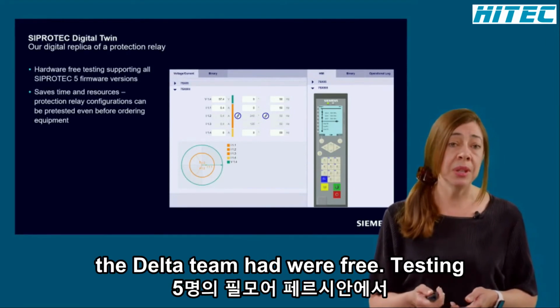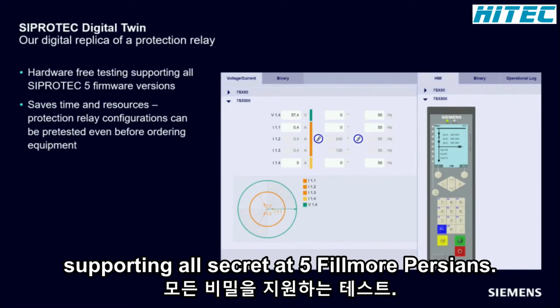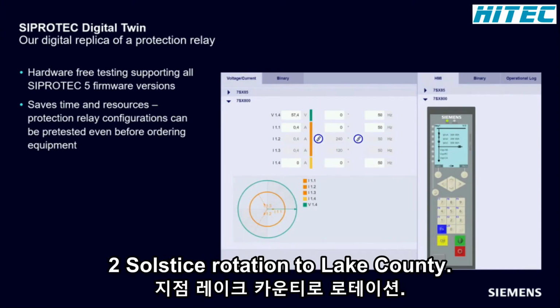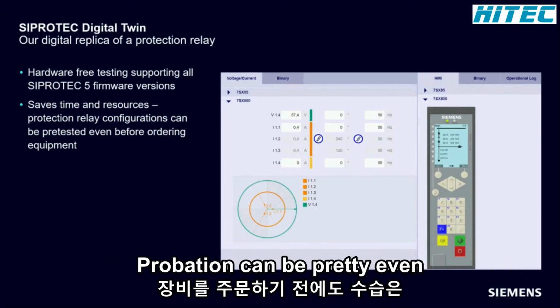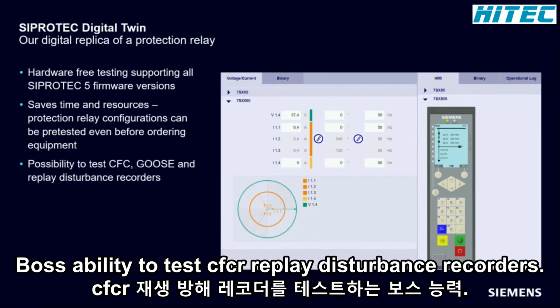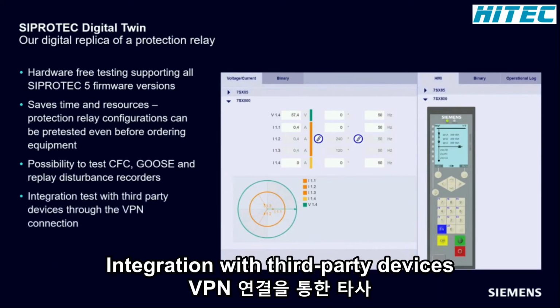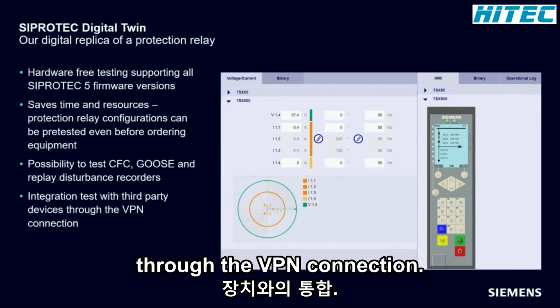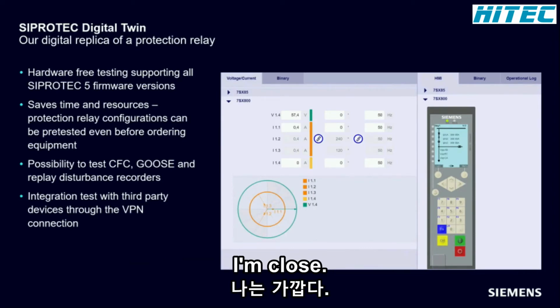In summary, with the digital twin, you get hardware-free testing supporting all SIPROTEC 5 firmware versions, save time and resources. Protection relay configuration can be pre-tested even before ordering equipment. Possibility to test CFC, GOOSE, and replay disturbance recorders. Integration tests with third-party devices through the VPN connection.